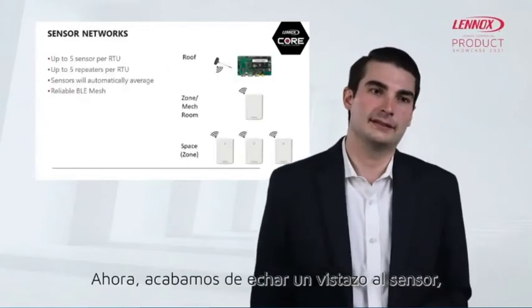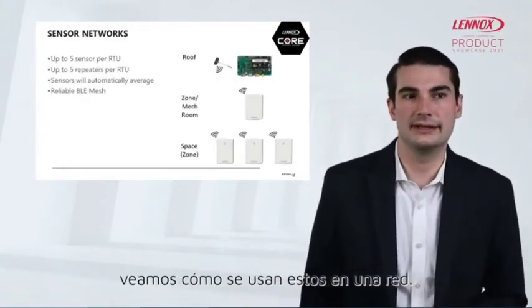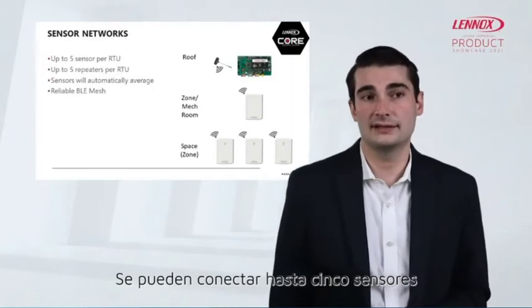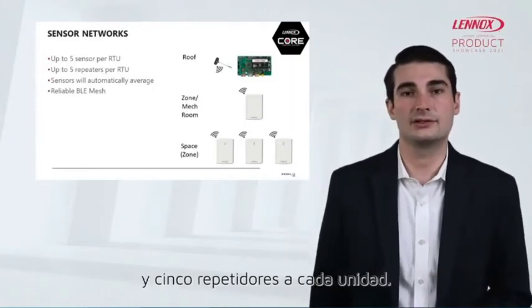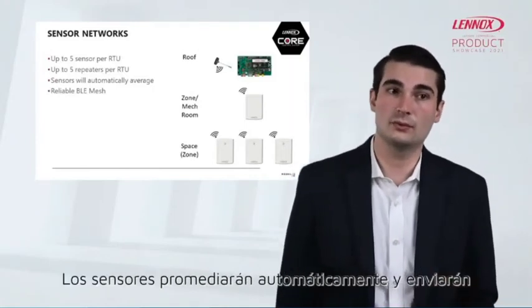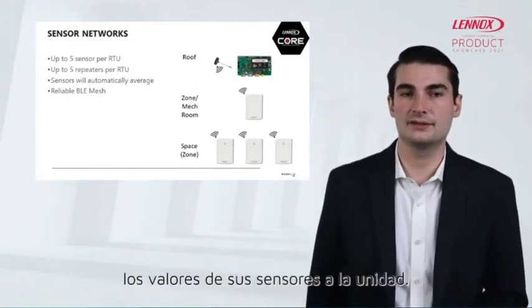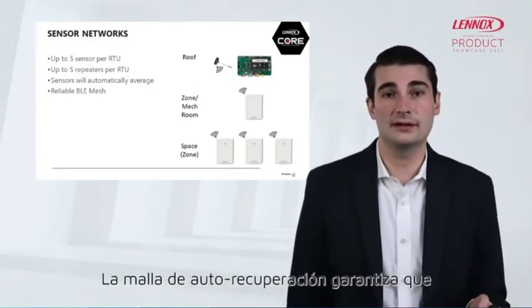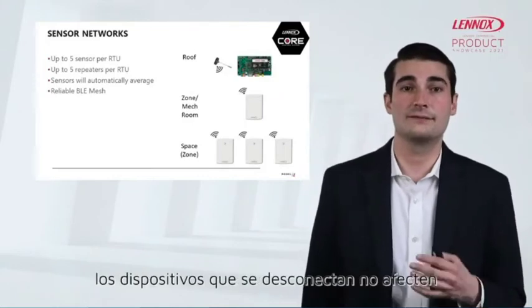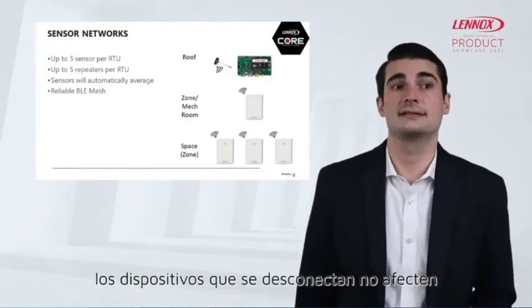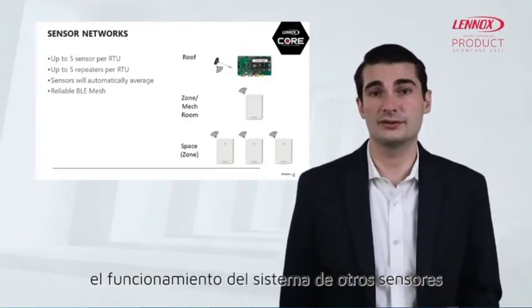Now we just took a look at the sensor. Let's see how these are used in a network. Up to 5 sensors and 5 repeaters can be attached to each RTU. Sensors will automatically average and send their sensor values to the RTU. The self-healing mesh ensures the devices that fall offline do not impact system operation of other sensors and repeaters that are still connected.